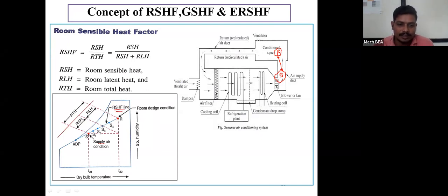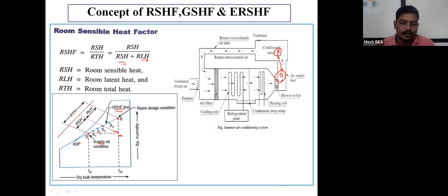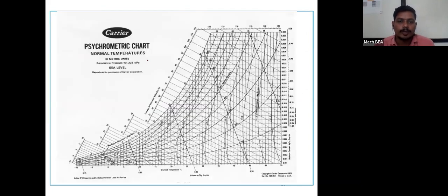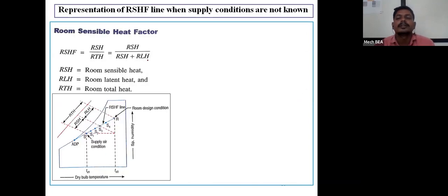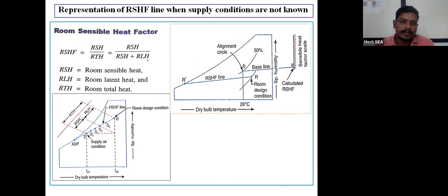This RSHF line can be divided into two parts. From S to point A, room sensible heat is added, and from A to R, room latent heat is added. So RSHF is room sensible heat divided by room total heat, whereas room total heat is room sensible plus room latent. After that, we saw how to represent the RSHF line when the supply air condition is not known.